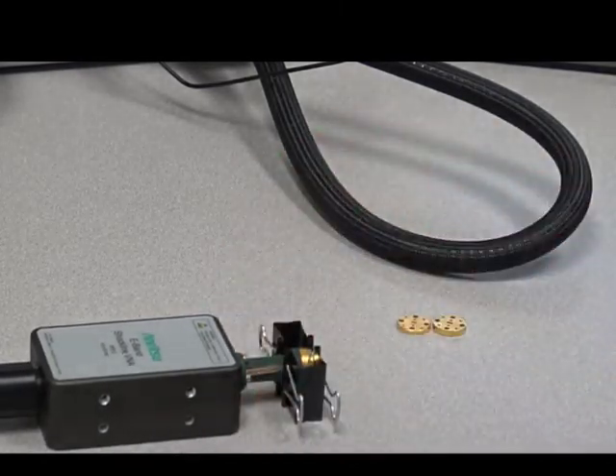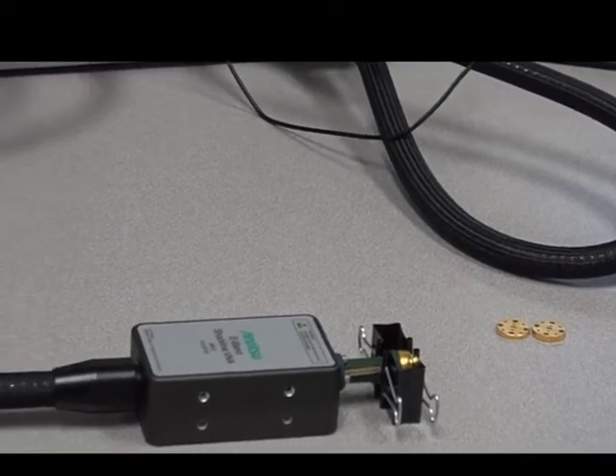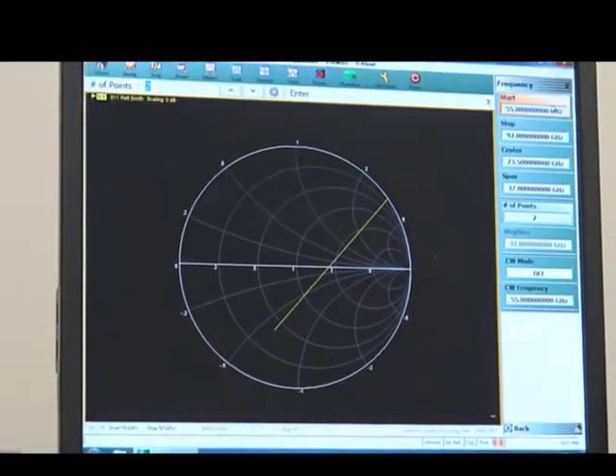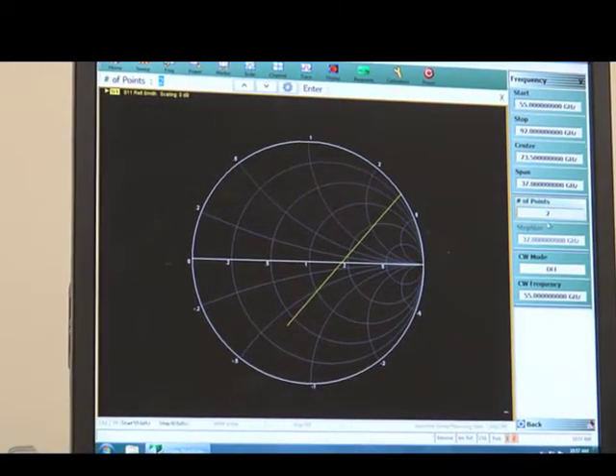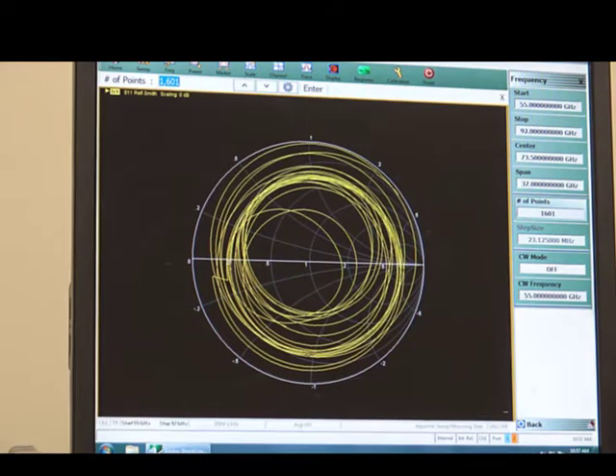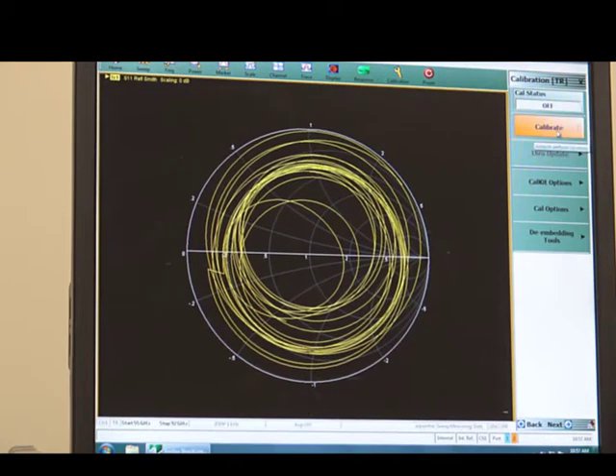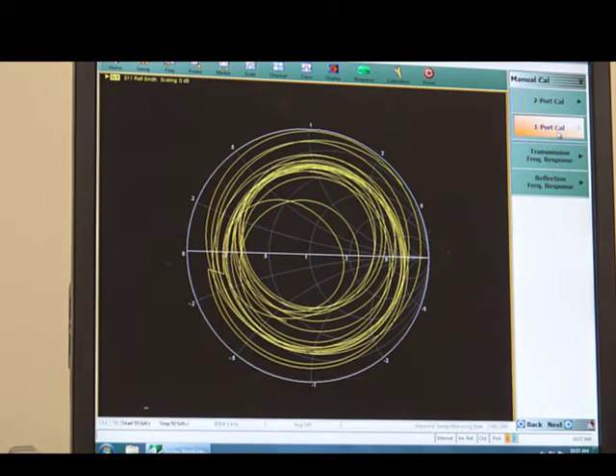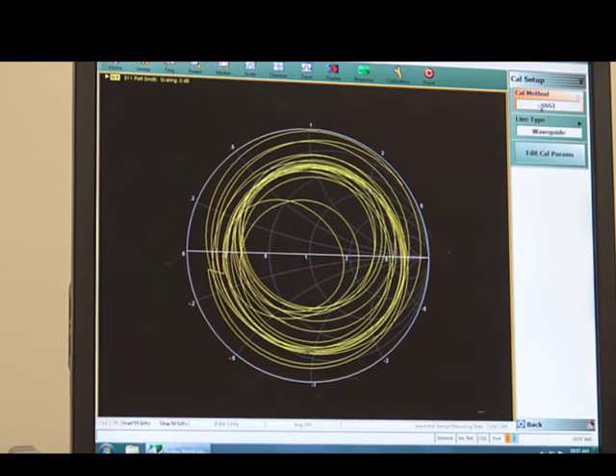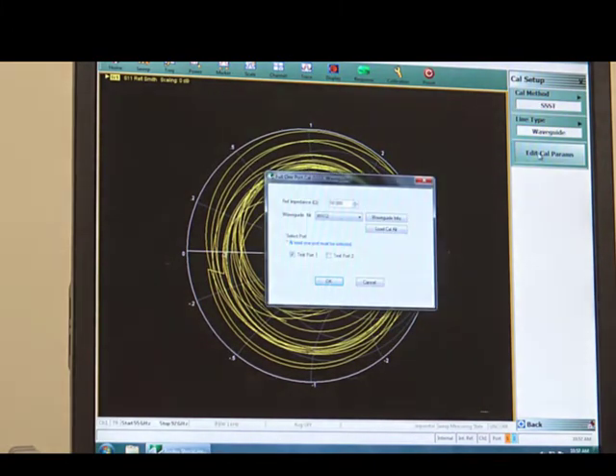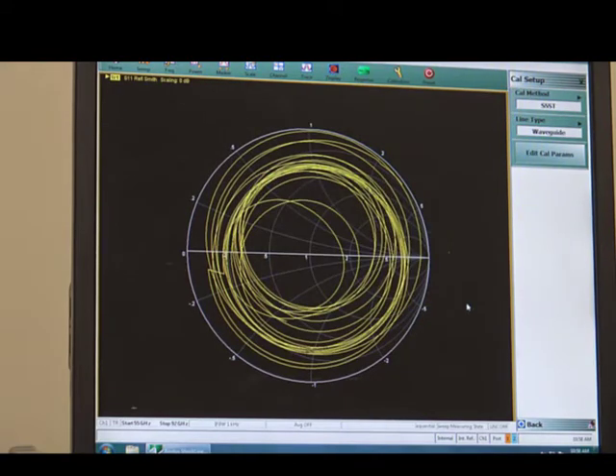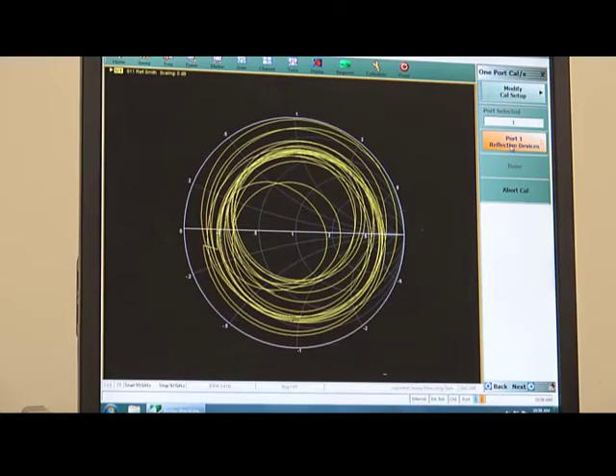Okay, so once you've done that, you go to frequency over here. Basically, it's from 55 gigahertz to 92 gigahertz, and the number of points I put is 1601. Then I go to calibration, and I select menu cal, which is 1 port cal, and then modify. This is going to be triple offset shorts, waveguide, and I did the cal parameter. WR-12 is already there, and I only do the test port 1 calibration. If you look at the waveguide information over here, it's exactly 2 millimeter, 2.8 millimeter, 3.6 millimeter for 3 different offset lengths. Okay, so I'm doing port 1 reflection devices.